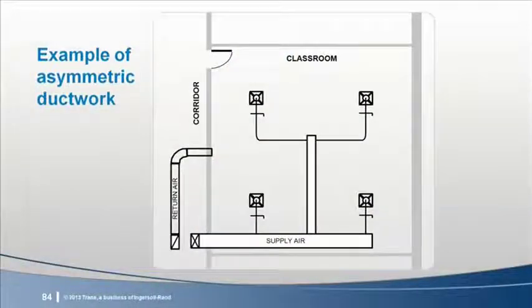For example, when the fan is operating at a design airflow of 2,000 CFM, the system is balanced to deliver 500 CFM to each of the 4 diffusers. But when the fan speed reduces to deliver 1200 CFM, you probably won't get exactly 300 CFM from each diffuser. More air will come out of the diffusers closer to the fan, and less will come out of the diffusers with the longer duct runs. The amount of variation depends on many factors, including the relative duct lengths and the number, type, and proximity of the duct fittings, so it's not easily quantified. So keeping the duct runs as short and symmetric as possible is general good guidance.